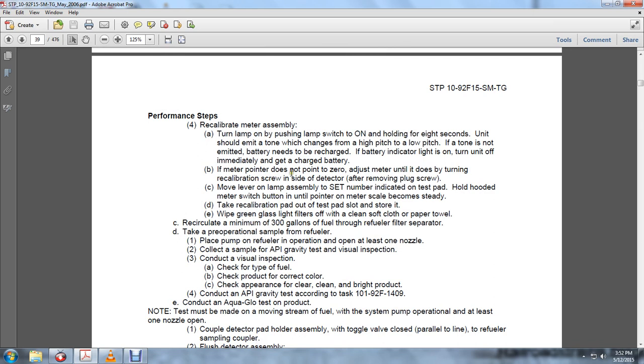B. If the meter does not point to 0, adjust the meter until it does, turning the recalibration screw inside the detector after removing the plug screw. C. Move the lever until the lamp is set to the number indicated on the test pad, holding the hooded meter switch button until the pointer on the meter scale becomes steady. Take the recalibration pad out of the test pad slot and store it. Wipe the green light filters with a clean soft cloth and paper towel.